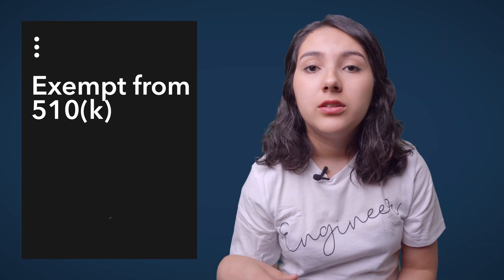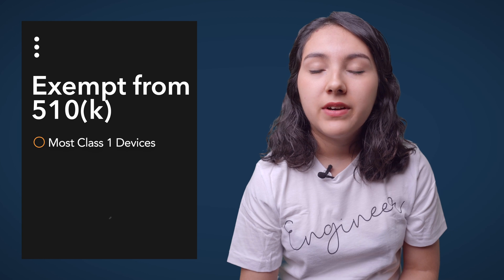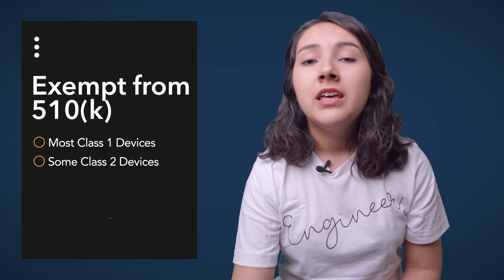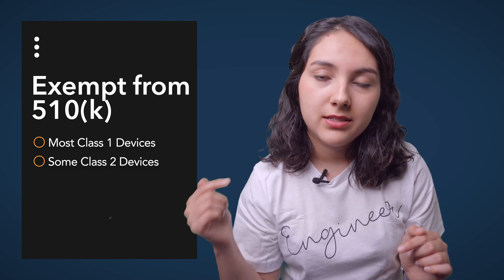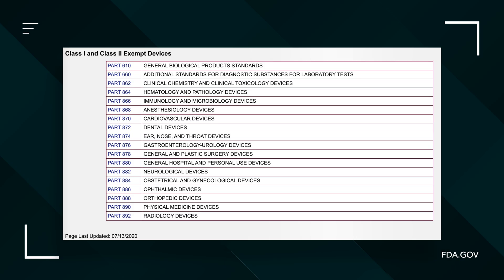There are actually a number of devices that are exempt from having to get a pre-market notification or submitting to the FDA. These include most class 1 medical devices and some class 2 medical devices. There is a list on the FDA website — FDA.gov — of the class 1 and 2 devices that are exempt from having to get any sort of approval or clearance before going to market. However, even though you don't necessarily need approval or clearance, you do need to register your company and provide your classification of device or your intended classification on the FDA's website.